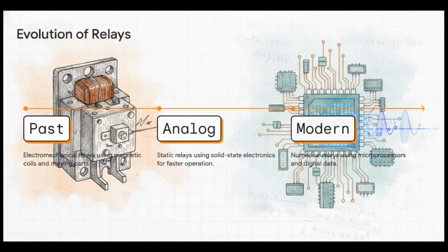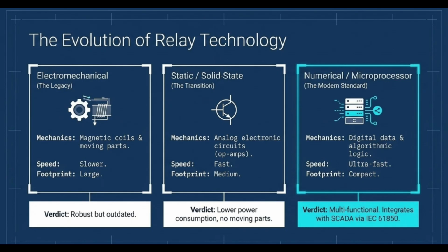It's honestly pretty wild to look at how this tech has evolved over the years. We started way back with traditional electromechanical relays. These literally used magnetic coils and actual moving mechanical parts to close contacts. In short, they were highly robust, but they were also incredibly slow to react and took up a huge amount of physical space. From there, we moved to analog static relays. These swapped out the moving parts for solid-state electronics like transistors, which gave us faster operation and lower power consumption.